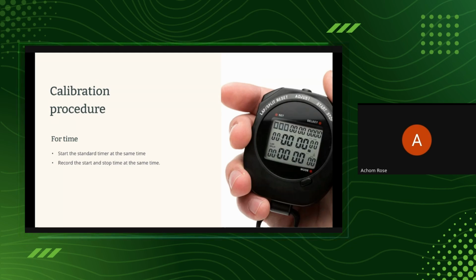You may decide that maybe sterilization time is not easy for me to use to calibrate. Then you look for another stage, because at the end of the day, you're calibrating the timer. So it is irrespective of which stage that you want to actually calibrate, because this timer is the same timer that you're using to set the drying time. It is the same that you're using to set the sterilization time. So we just want to verify the performance of the timer. Okay, so you will start and stop, and then you read the standard and the unit under test or the UUT, right?